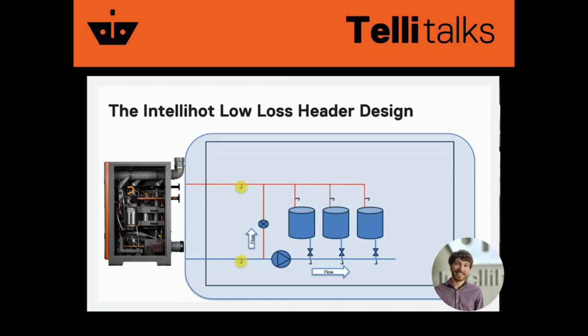So your heat exchangers, say you've got your unit set to 140 degrees. The minute I start bypassing water through the bypass line, my heat exchangers start to fire a little bit above 140 degrees. Now I'm delivering water from my heat exchangers at 150, 160. Okay, and that's mixing with the water at the outlet, which is providing the temperature that's desired to the fixtures.